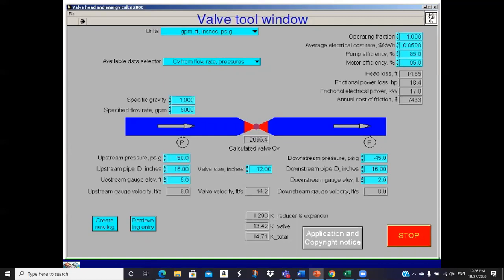So you can calculate CV from your flow rate and pressures, if that's what you know, or you can calculate your flow rate from your CV and your pressures, or you can calculate your upstream pressure from the other 3, or you can calculate your downstream pressure from the other 3. You've got to have 3 of the 4, or be willing to guess. Okay, so you set this pull-down menu on whichever you want to consider the unknown and the knowns. Put in your specific gravity. In this case, we're going to calculate the CV, so we have to put in a flow rate. So the flow rate is 5,000. We put in an upstream pressure. We put in a downstream pressure.